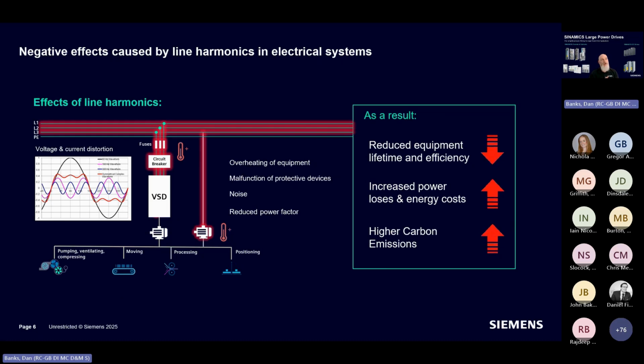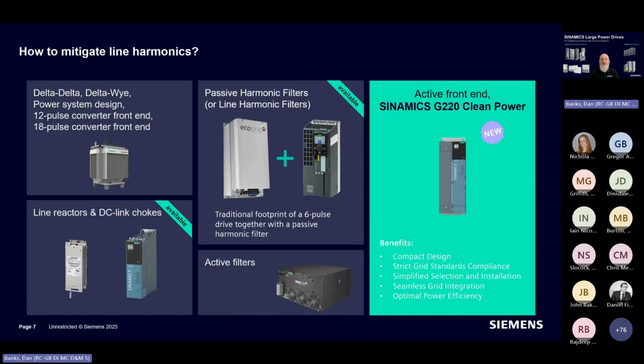And I've seen sites where they've had catastrophic failures to transformers, and they could look at their data and 100% say this was because our harmonic content was too high. So that's our challenge, and that's what we need to address. And there are typically a couple of ways of addressing that. If we go back 20, 30 years in the drives industry, it was the idea of multi-pulse converters. So you'd have a 12 pulse or an 18 pulse front end, by which I mean you take a standard drive and you parallel up the inputs.